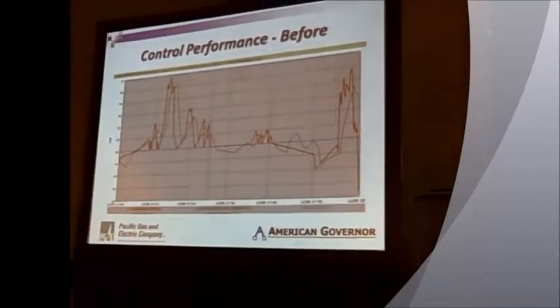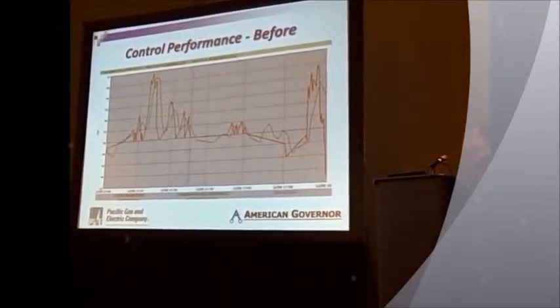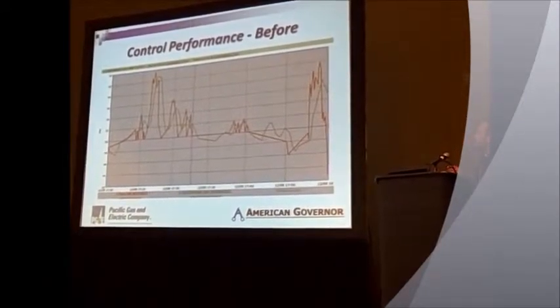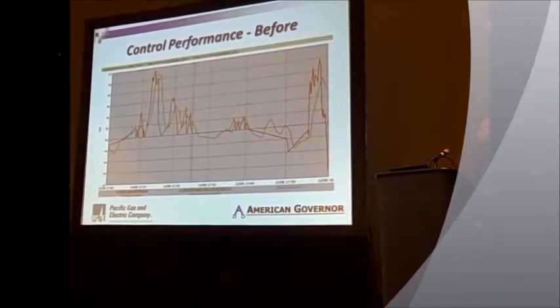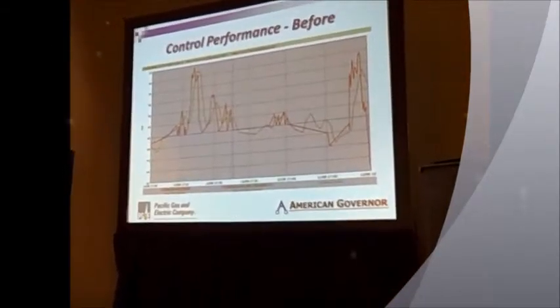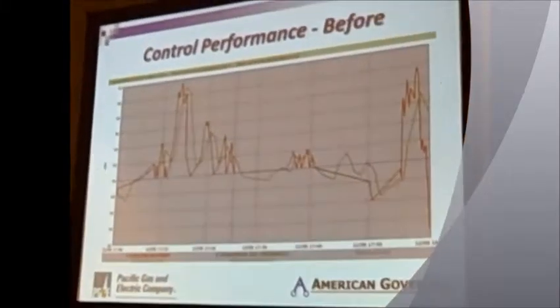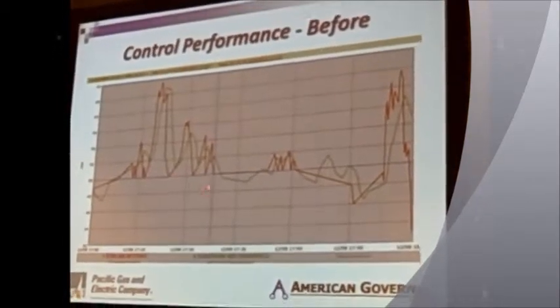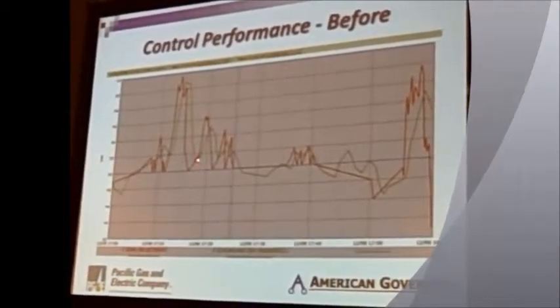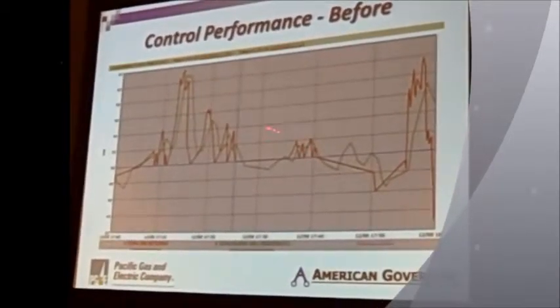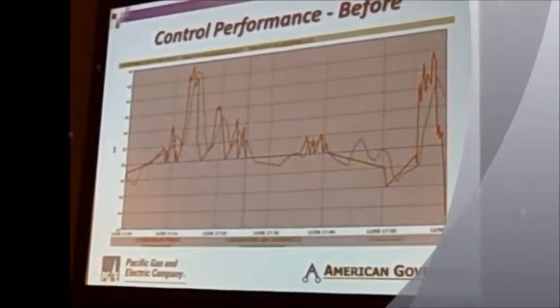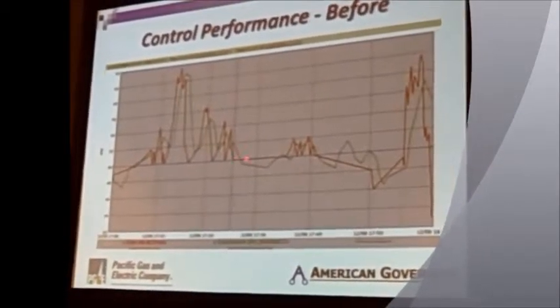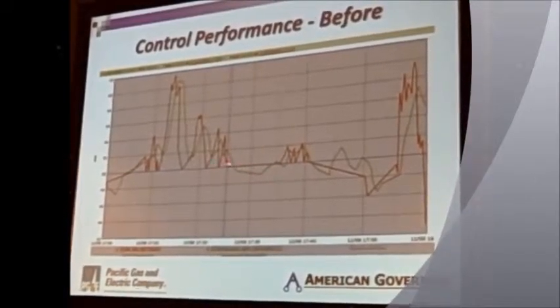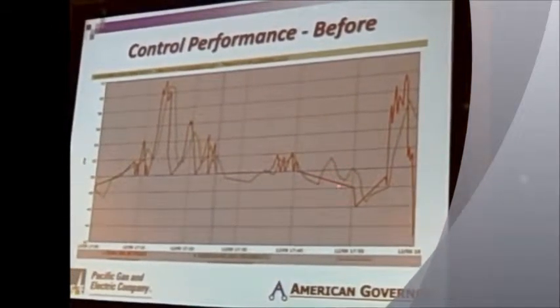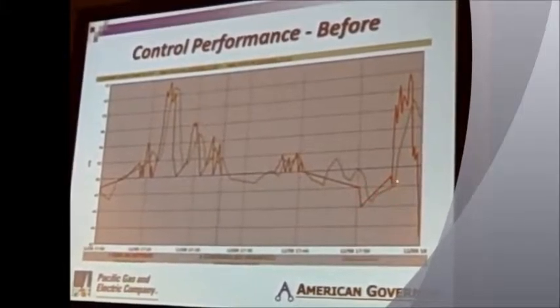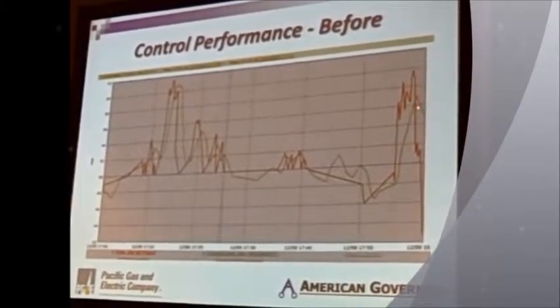So to performance, this is a 1 hour time slot of the old mechanical governor, with the red line being the set point from the ISO, and the green line being the governor, the actual megawatts out of the unit. And what I want to point out are the lags in response to set point changes, but more importantly, the hunting you're going to see around here, here, and here, where the actual megawatts are deviating away from the set point, and sometimes in an uncontrolled manner. Also, you can see here a significant lag in following set point.